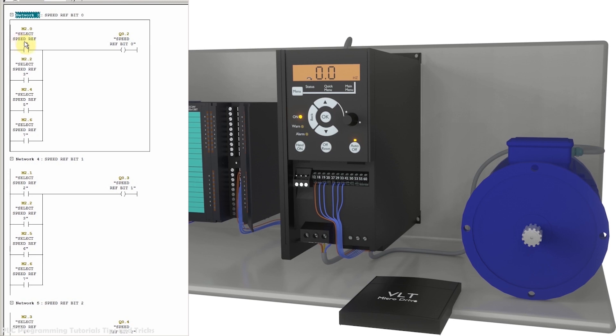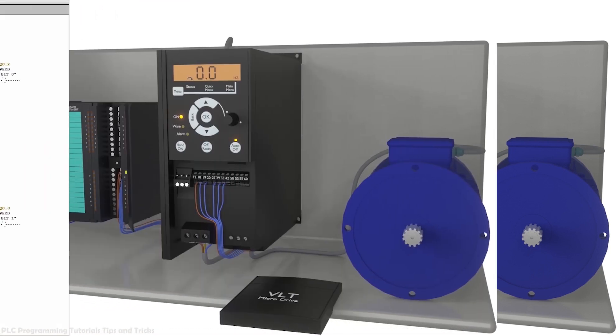In network 3, turning on bit M2.0 activates output Q0.2 (speed reference bit 0) and the VFD loads preset frequency 1 — 2.5 Hz. Turning on M2.1 activates Q0.3 (speed reference bit 1) and the VFD loads preset frequency 2 — 5 Hz. Turning on M2.2 activates both bit 0 and bit 1; their sum is 3, loading preset frequency 3 — 7.5 Hz. Similarly, bits M2.3 through M2.6 load the fourth through seventh preset frequency references.